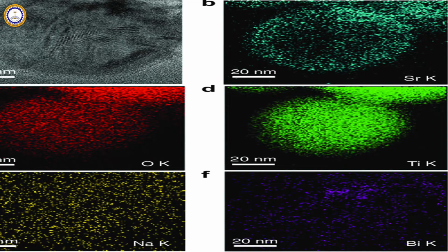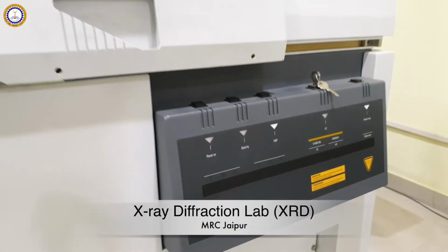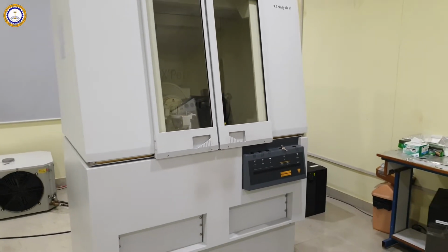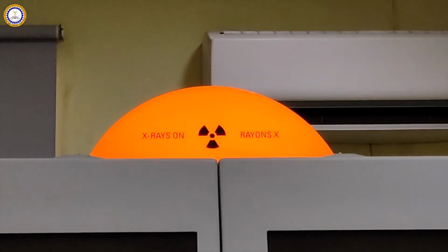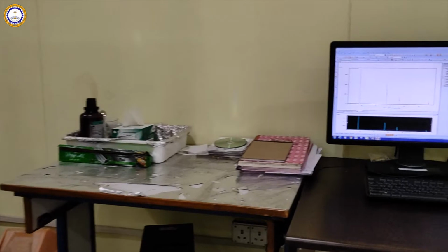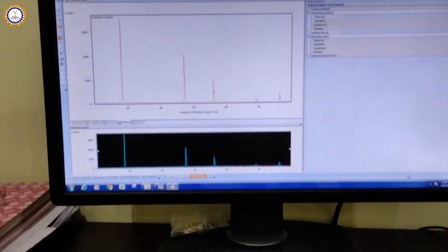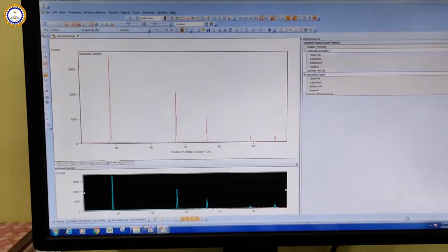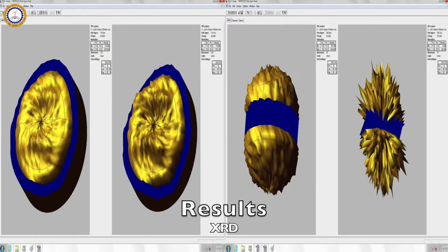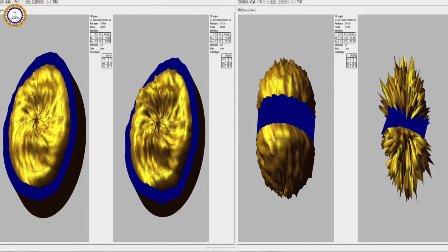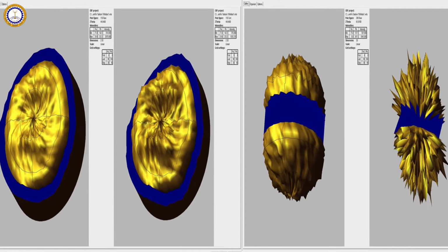This is the PANalytical X-ray diffractometer, which can give information on the 3D arrangement of atoms in a material. It can be used to reveal structural information for powders, thin films, and bulk samples. The diffractometer can be configured into Bragg-Brentano configuration, offering high-resolution and high-beam-intensity analysis. It is also capable of collecting diffractograms, which represent orientation distribution functions, which map a set of pole figures of crystallites of interest.